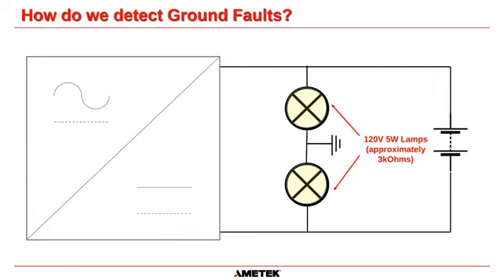And the most basic form of ground fault detection is 2 lamps connected in series with the center point of the lamps connected to ground. Okay? This is the most basic form of ground fault detection. Now, these are 120 volt, 5 watt lamps. We're saying approximately 3 kiloohms.